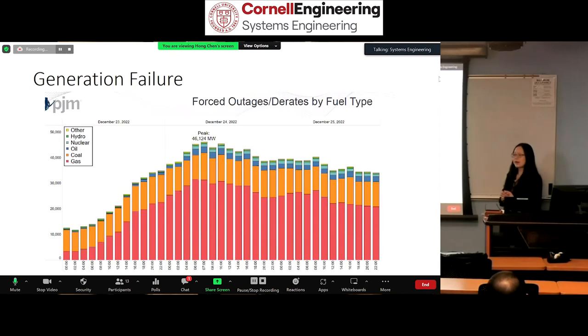And most of them were gas units. Because of the gas units, besides the equipment issue at the power plant—because the equipment was too cold—the other big issue was gas supply. Basically, the wellhead froze, so there was no gas coming from the pipeline, or either because gas was too expensive. When we called the generation online, they'd say either the unit was running until it tripped offline due to failure, or they'd say there's no gas—I cannot come out, no gas.